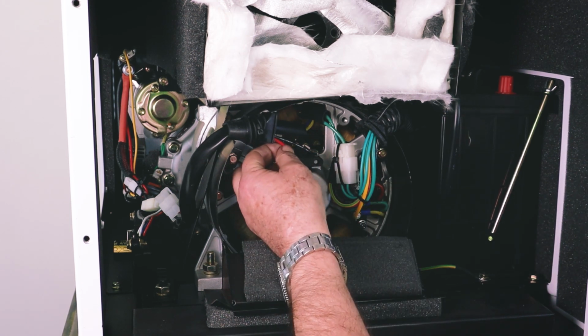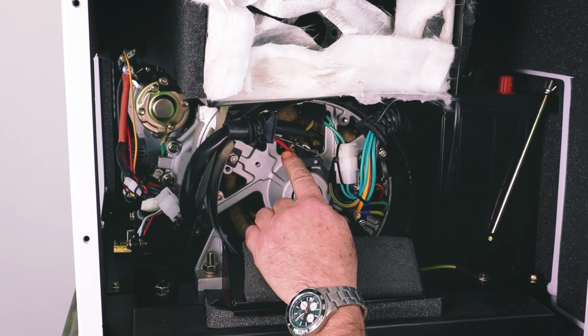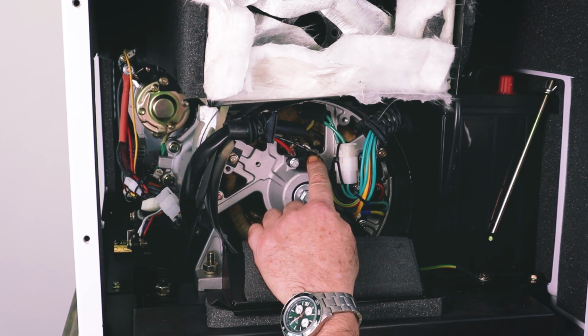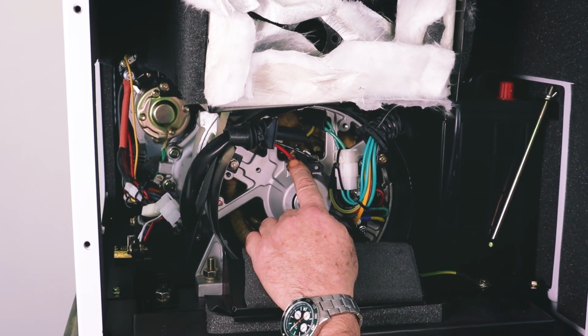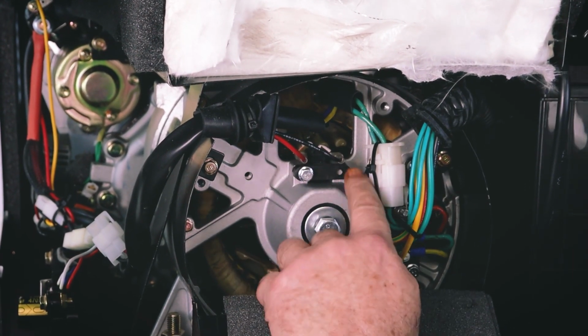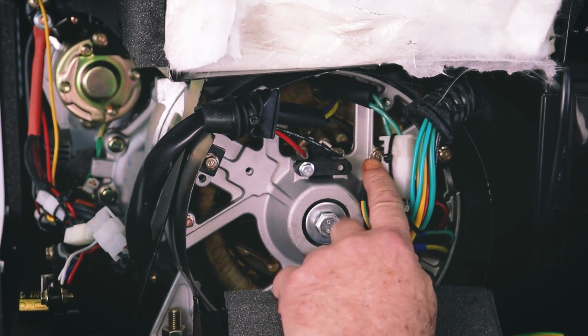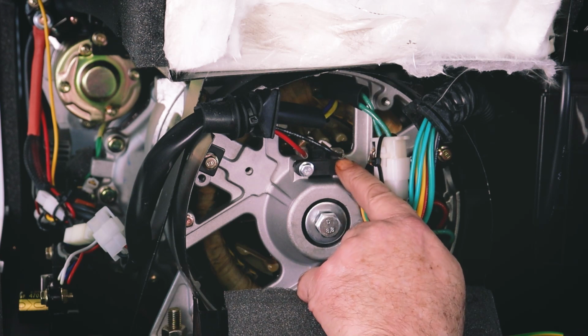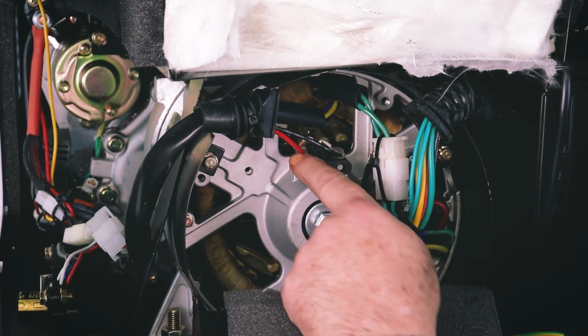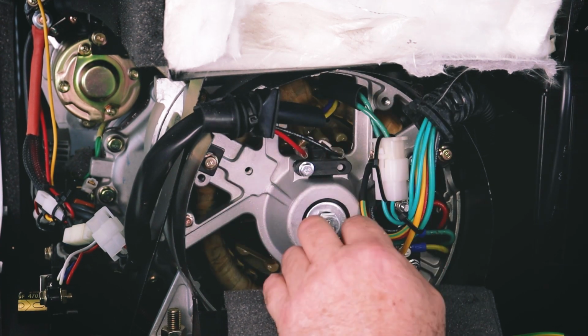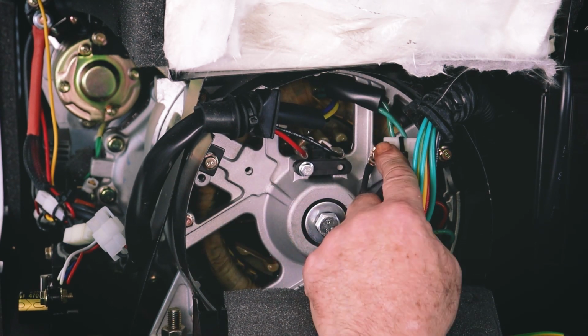As I said earlier, these 2 wires here—red always on the left and black always on the right—are the power coming onto the brushes from the AVR. Again, a visual check first: have we got any burning? Are these connectors on? Have we got a broken wire? If not, we've got to dig a little deeper.